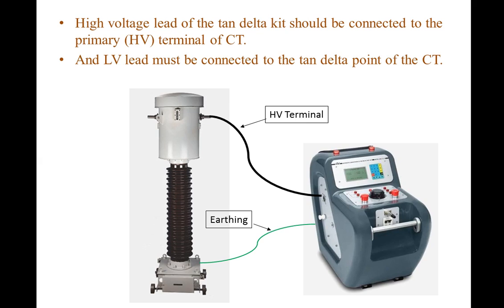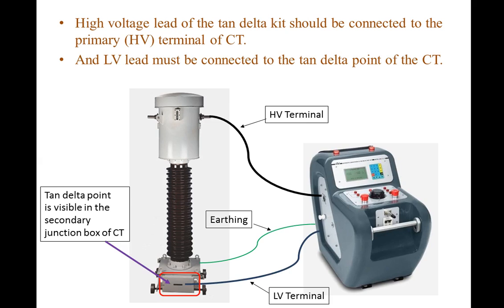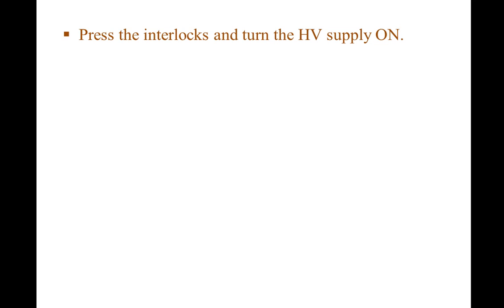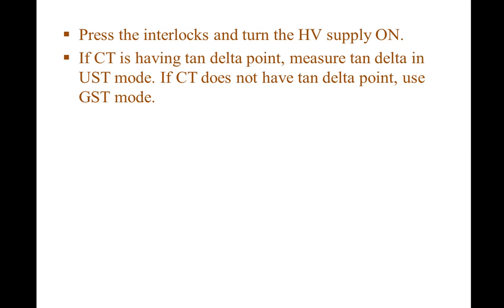The high voltage lead of the tan delta kit should be connected to the primary terminal of the CT, and the low voltage lead must be connected to the tan delta point of the CT. The tan delta point is visible in the secondary junction box of the CT. If the CT has a tan delta point, measure tan delta in UST mode. If the CT does not have a tan delta point, use GST mode.